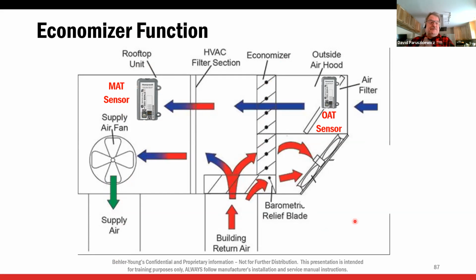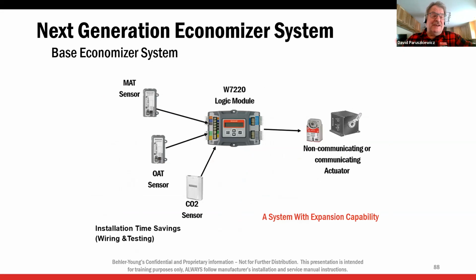The barometric relief is because we're dumping air into the building. We're going to pressurize the building. We have to let it out. It could be a damper, or on big units, it could be a fan. If it gets too hot and too humid outside for air conditioning, then the compressors will come on, these dampers will close, return will open, and it will do normal mechanical cooling. If we have a two-stage unit, let's say it's 65 outside, low humidity, we're going to economize because it's 80 inside, and we're bringing cold air in, and our thermostat calls for second stage cooling. Then with the economizer open, it will bring the first stage compressor on. Okay, so always use a two-stage thermostat when using an economizer. Even on a 3-ton unit, if you got an economizer, use a two-stage stat so that you can bring second stage cooling in with the economizer if you need to.